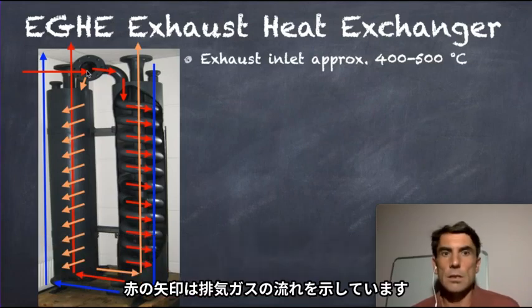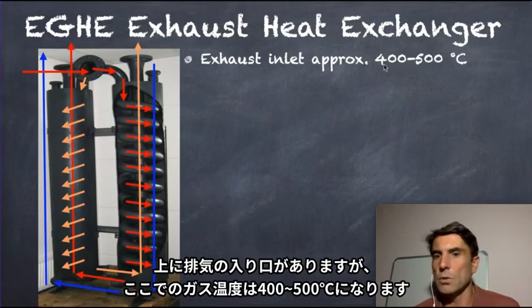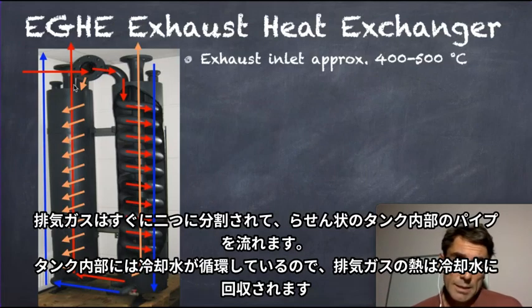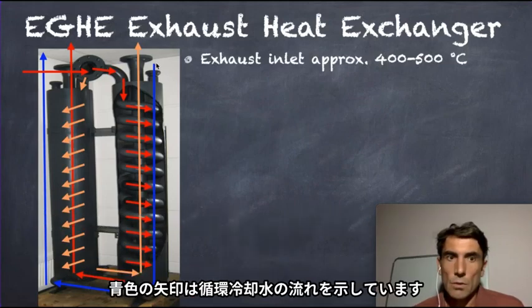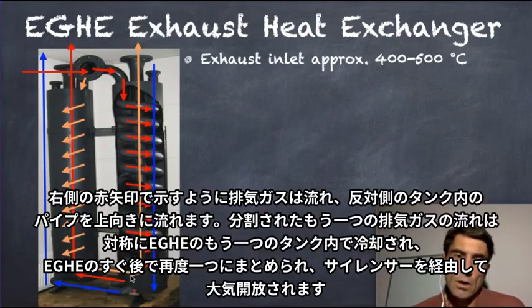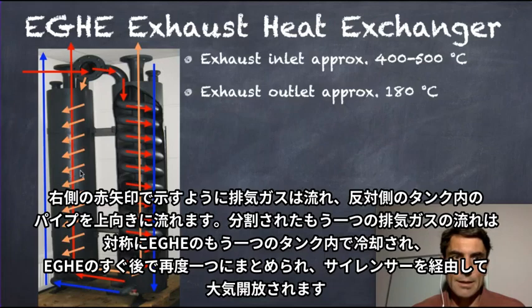For example, the red is the supply from the exhaust gas. So this is the inlet. We're running into here, approximately, depending on the version or on the CHP, between 400 to 500 degrees. We split that into the two tanks. We run it through this circulation pipe through the tank. In the tank we have water. We have the water supply on the top. The water runs to the bottom. So the heat from the exhaust gas will now transfer through this ring pipe to the water. From here we're running through the red and going directly through the other pipe up to the exhaust gas outlet. From the other one, it runs down through the ring pipe, goes back to the other and goes up.